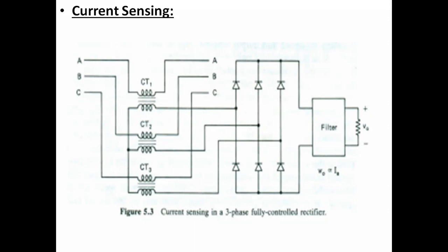Coming to the frequency, the frequency of the ripple in the rectified current of a three-phase transformer will be 3 times that of the single-phase transformer. Because the ripple frequency is higher, the filter time constant will be lower, and it gives a faster response of the current control loop.